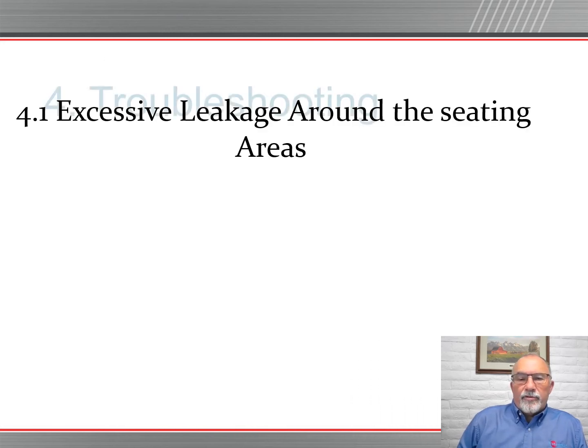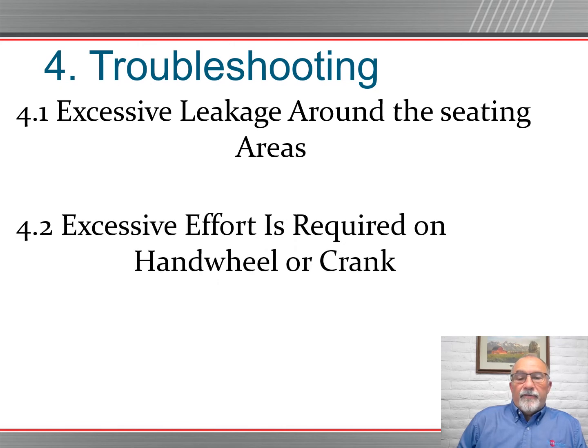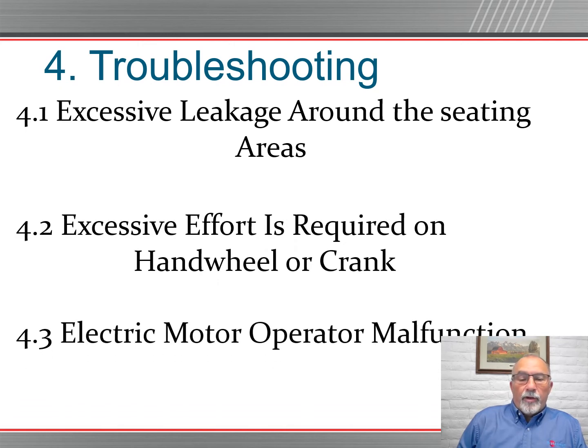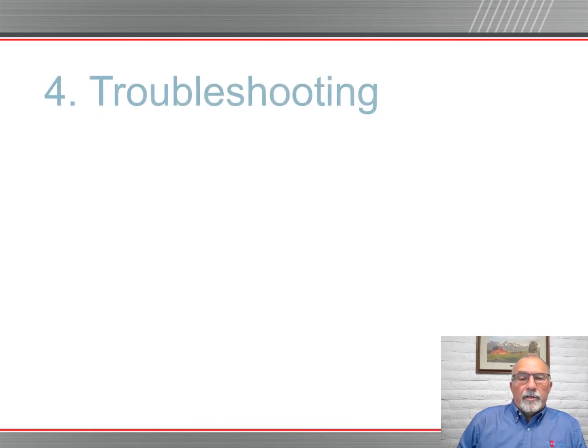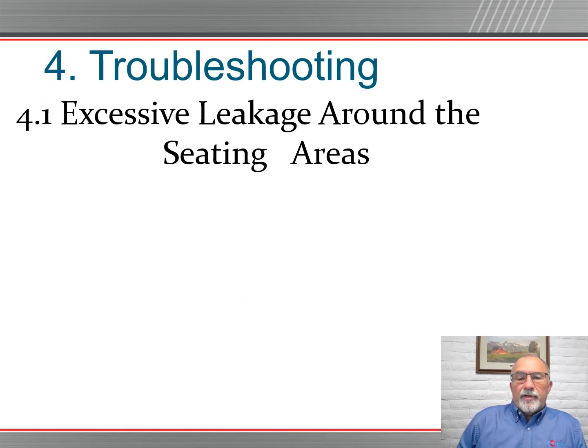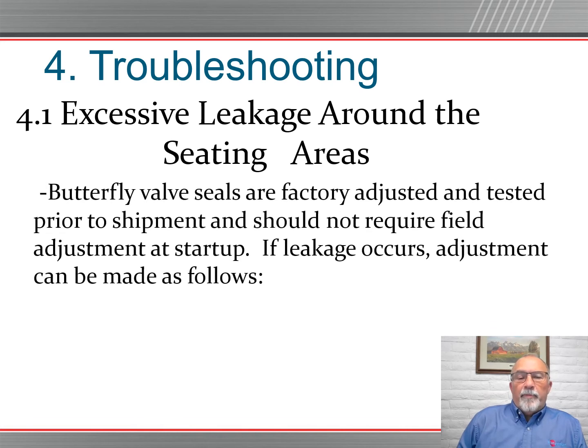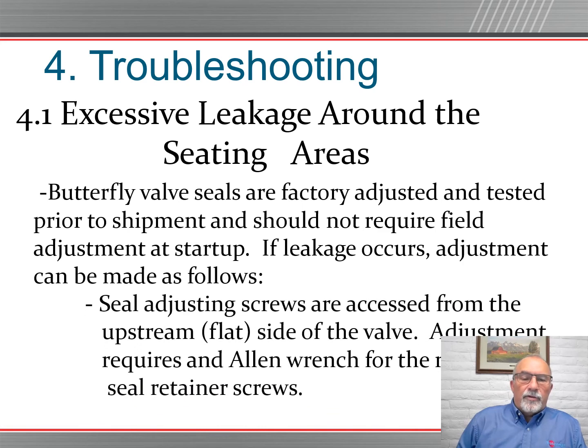Troubleshooting. Excessive leakage around the seating areas. Excessive effort is required to handle the hand wheel or crank, or the electric motor operator is malfunctioning. Excessive leakage around the seating areas can be solved as follows. Butterfly valve seals are factory adjusted and tested prior to shipment and should not require field adjustment at startup. If leakage occurs, adjustment can be made as follows. Seal adjusting screws are accessed from the upstream, the flat side of the valve, like I mentioned in a previous slide. Adjustment requires an Allen wrench for round head seal retainer screws, or just a standard 7/16 wrench if they're nuts.